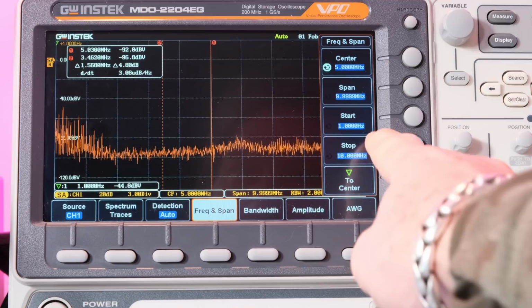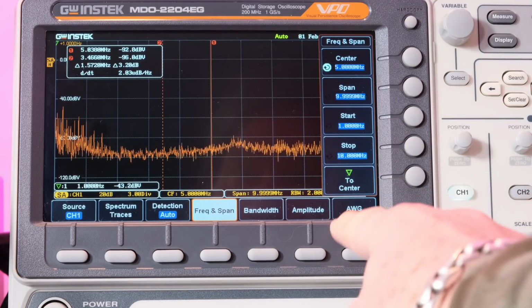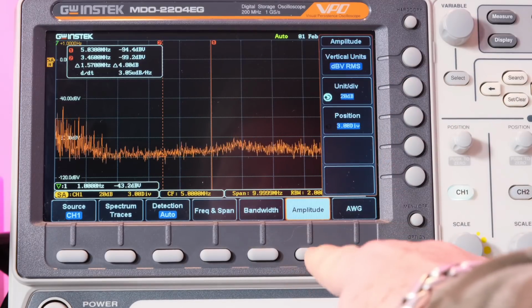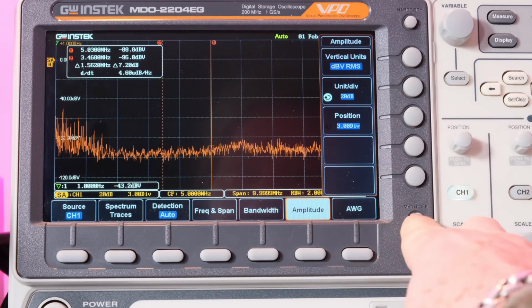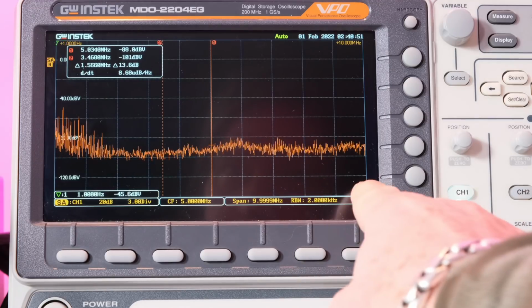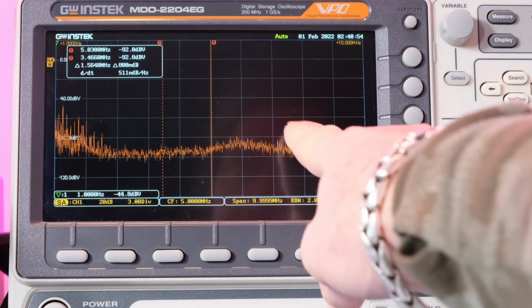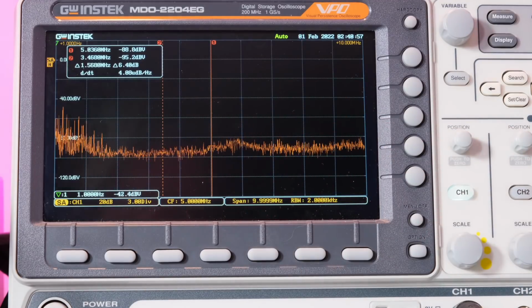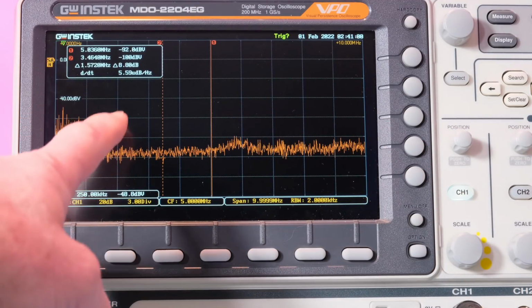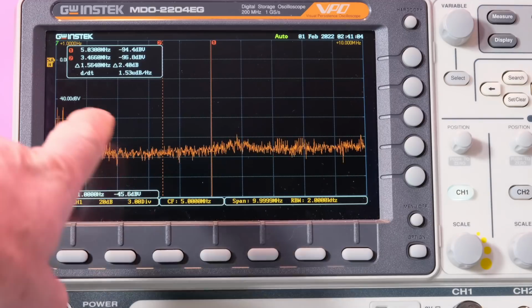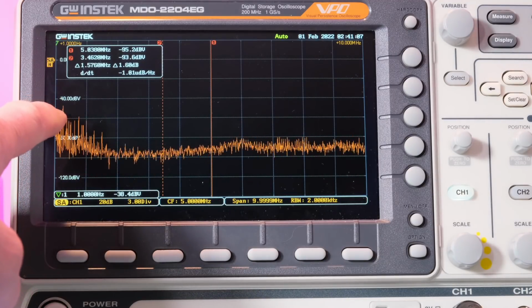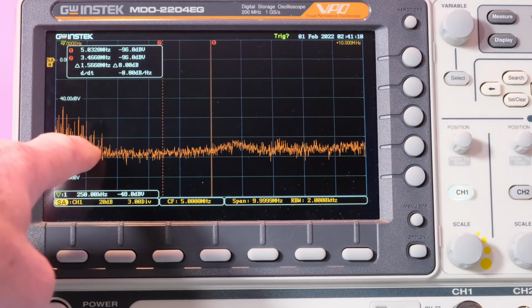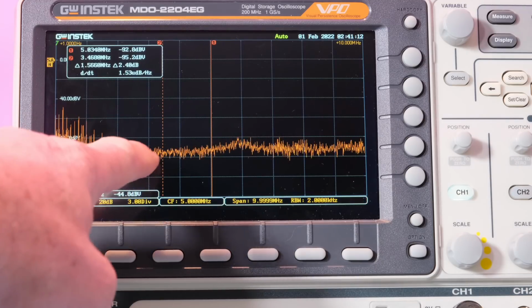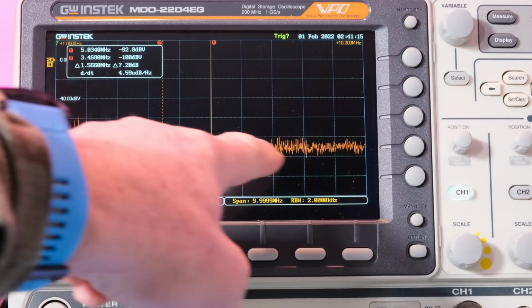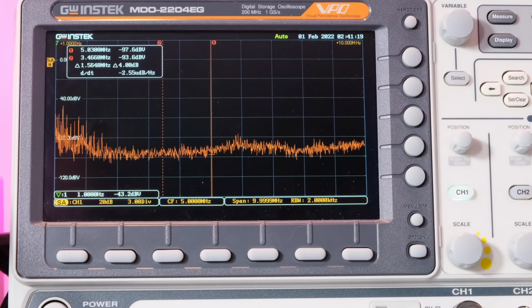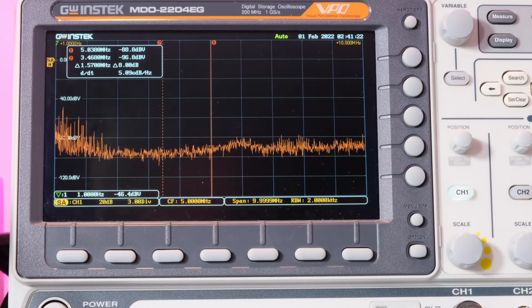So frequency and span, it starts at 1 hertz, ends at 10 megahertz. And amplitude 20 dB per division, okay? So we've got 10 megahertz out here, so each one of these bars is 1 megahertz. So we have 1 megahertz starting here, 2, 3, 4, and so on. Now this is minus 40, so you see we have some noise just below minus 40 in the first 1 megahertz, maybe first 2 megahertz, and then it drops down to about, this is at 80 dB, so that's pretty low. That's a low noise power supply, so that is actually looking pretty darn good. And that's with the load.